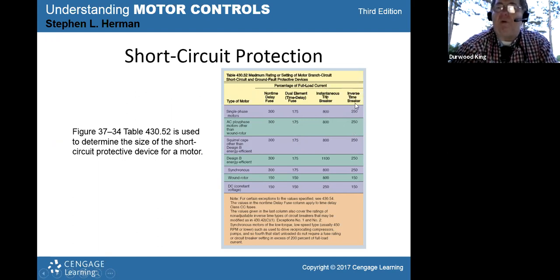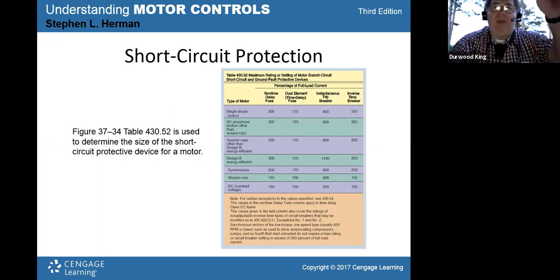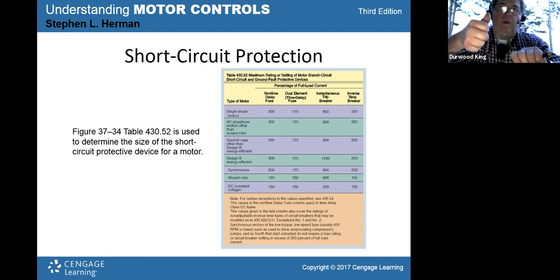So an inverse time breaker, the name inverse time means this: the higher you go above the breaker rating, the shorter the trip time becomes. So if the breaker is rated at 100 amps and you go to 110 amps, it's going to take that breaker quite a while to trip. But if you go with a 100 amp breaker and you draw 200 amps, then the time actually shortens as the amps increase, so they call it inverse time. The time gets shorter the higher the amps go. The actual trip time becomes quicker the higher you go in amps.